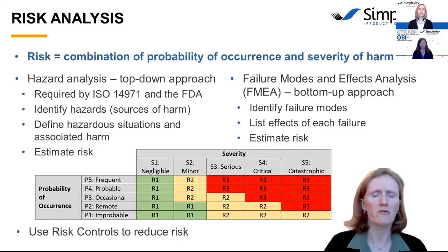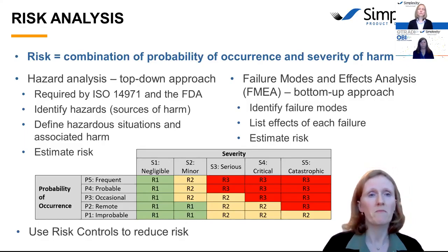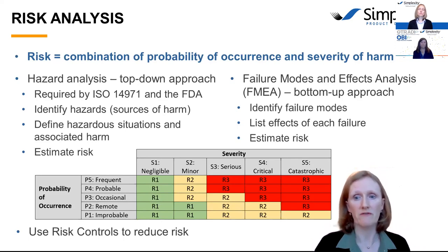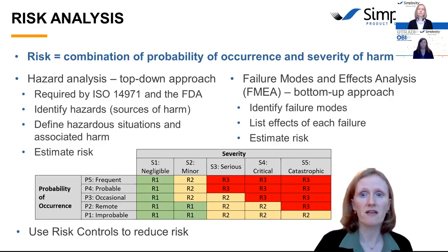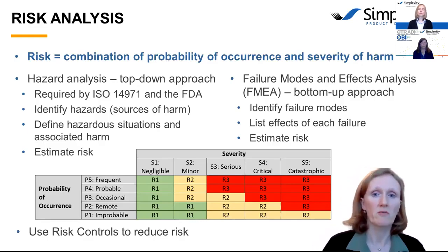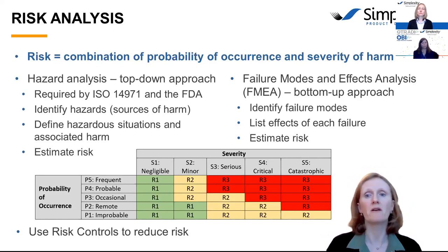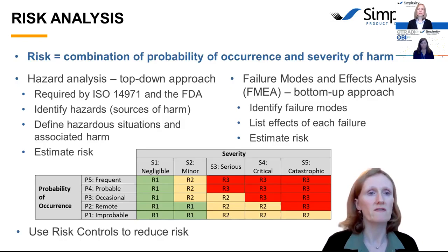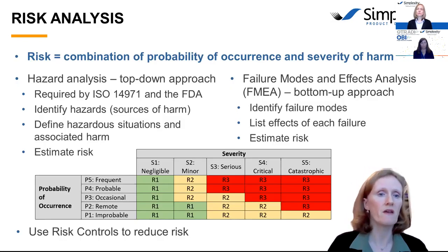So a risk level table, which I have an example of shown here, combines the probability of occurrence of harm with the severity of harm to estimate the level of risk. This table will be customized for our particular products, but they would look pretty similar. In red, with the R3, we have unacceptable risk, and further action is required to eliminate and continue to lower the risk as far as possible. Yellow also requires further action. It's unacceptable, but for residual risks that still remain in this region, you would do a risk-benefit analysis, without considering economics, and conduct that for each risk to show that the benefits outweigh the risk. The R1 boxes in green are acceptable risk and no further action is needed.